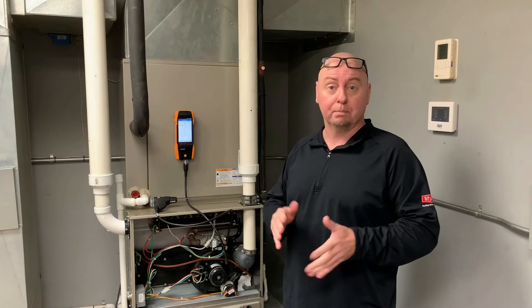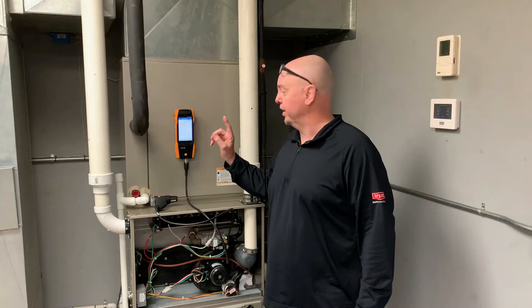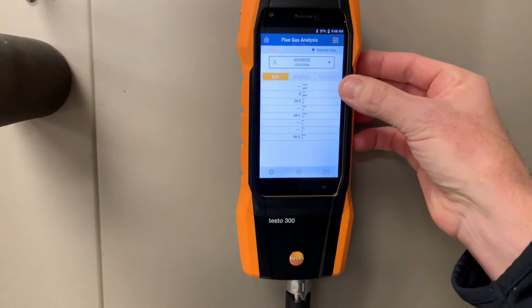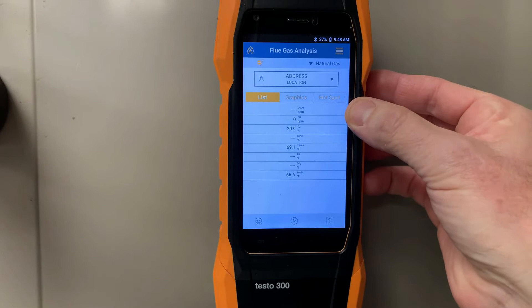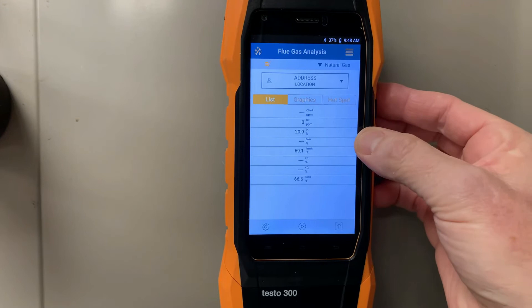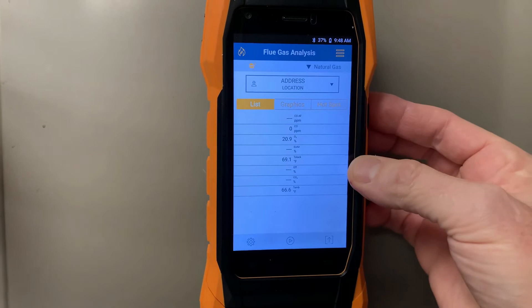Great people, great company, great employees, and we appreciate them letting us use their training facility. The meter I'm using here today is a Testo 300. The first thing on the meter at the top is where it's marked COAF — that means CO air free. That's the CO we're looking for inside of a flue pipe. The other thing we're looking for is the O2 level, currently at 20.9. We're mostly going to be looking at O2 and COAF.